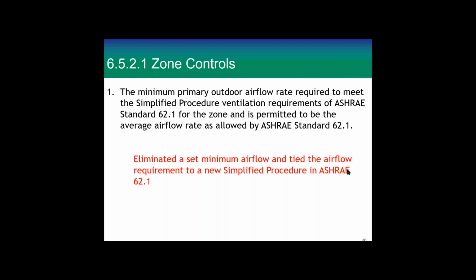And the simplified procedure, from what I can tell working on it, is easier to use than the spreadsheet that they gave us. If you buy ASHRAE 62, you get a spreadsheet, and you can go through and put more air in your spaces that are controlling how much percentage of outside air you get, so that those are no longer in control. It's better to put more air in there than to open your outside air damper that wide, so you can eliminate those. This simplified procedure removes that iterative approach, but your final answer is not quite as low as your possible final answer in the previous way.